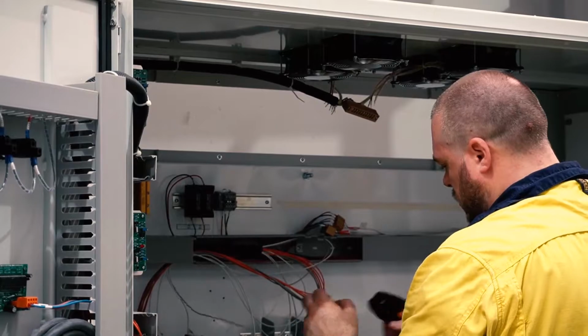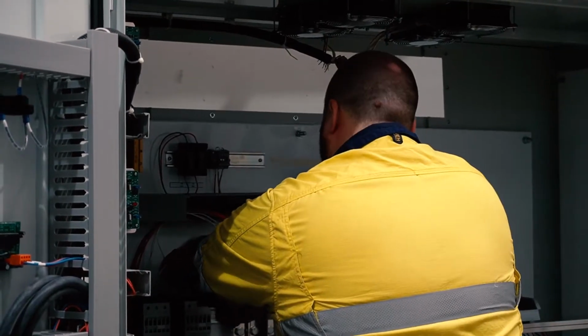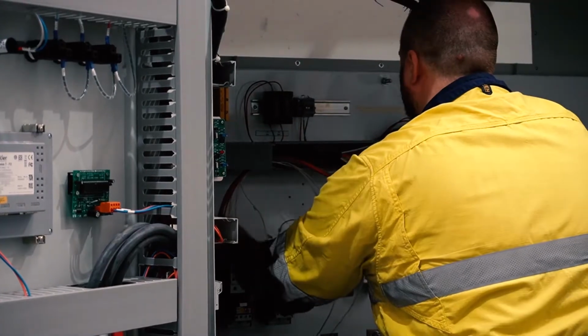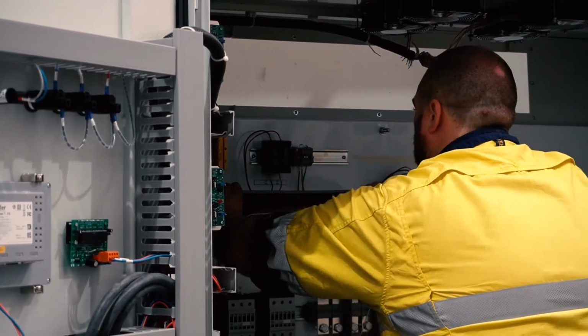And that increases the current quite substantially from, I think it's close to 80 amps from the wall all the way up to 3000 amps. The unit itself is generating hydrogen through electrolysis. Certainly the biggest thing that I've worked on.